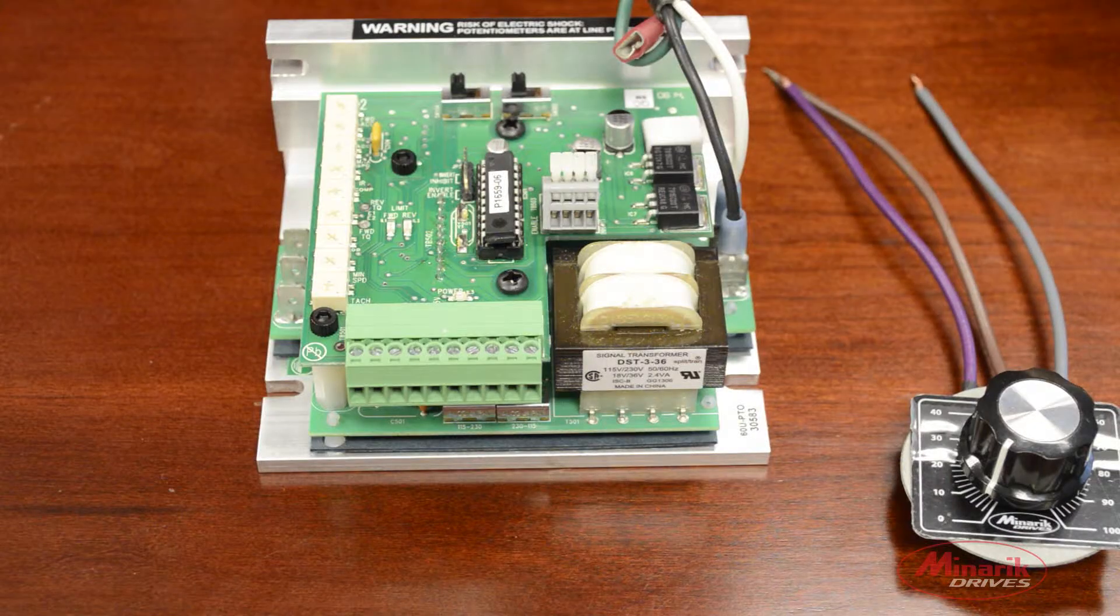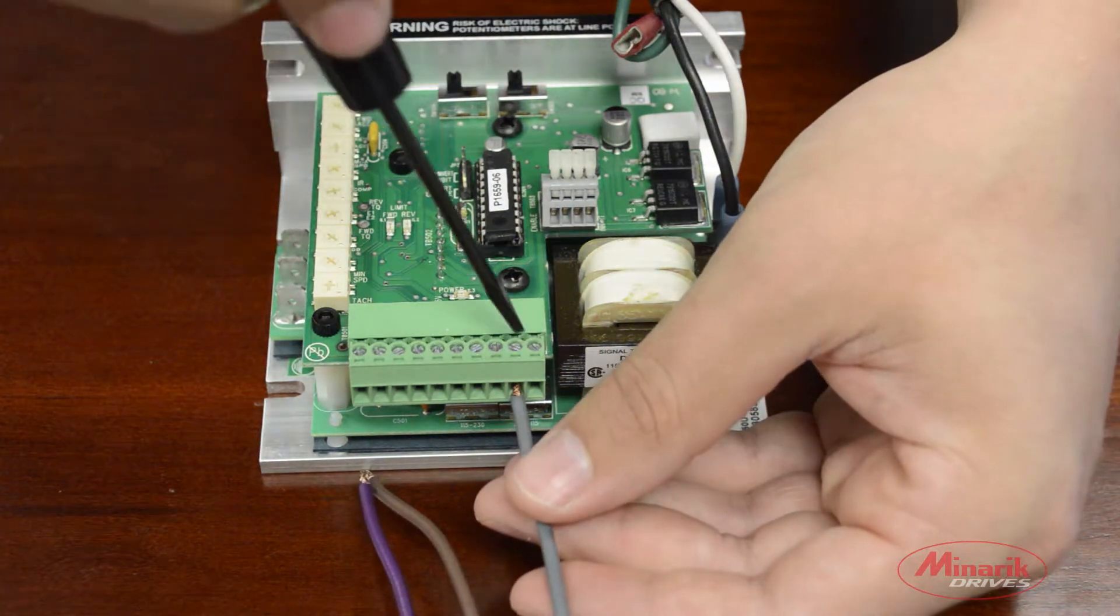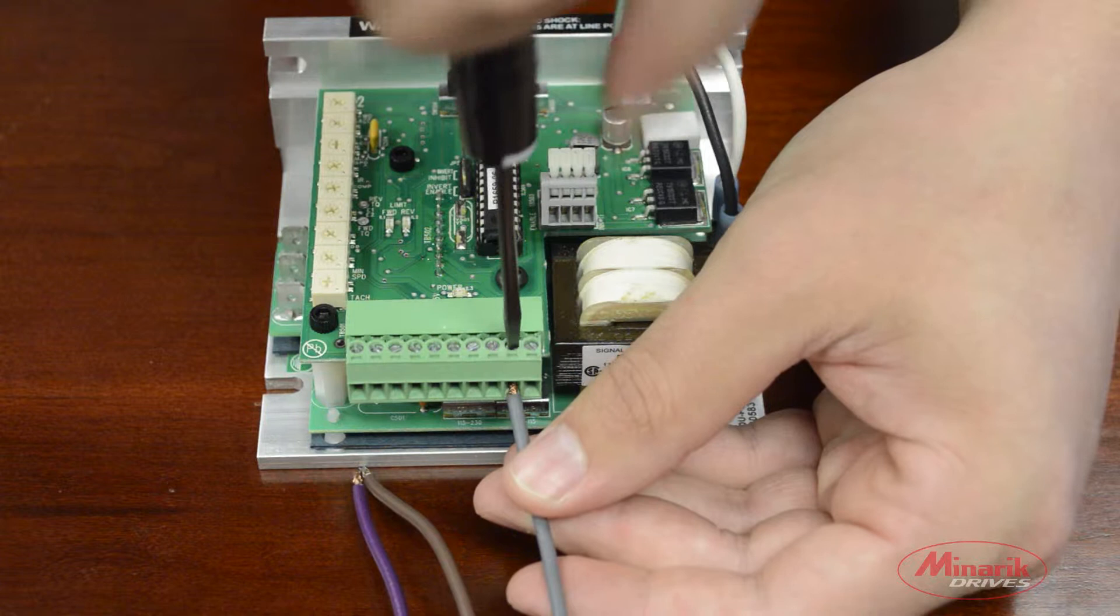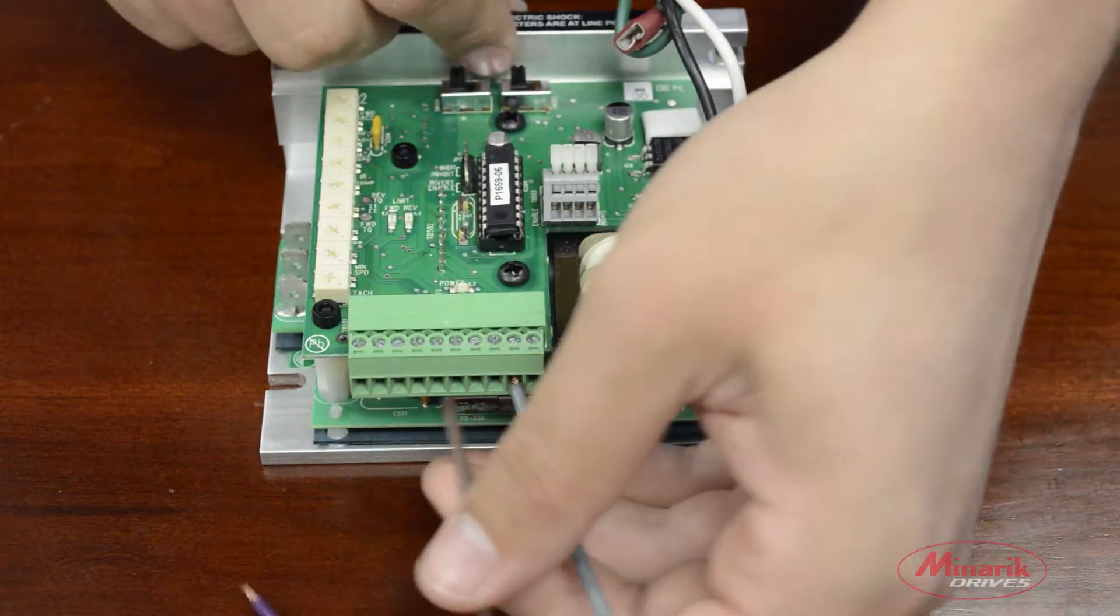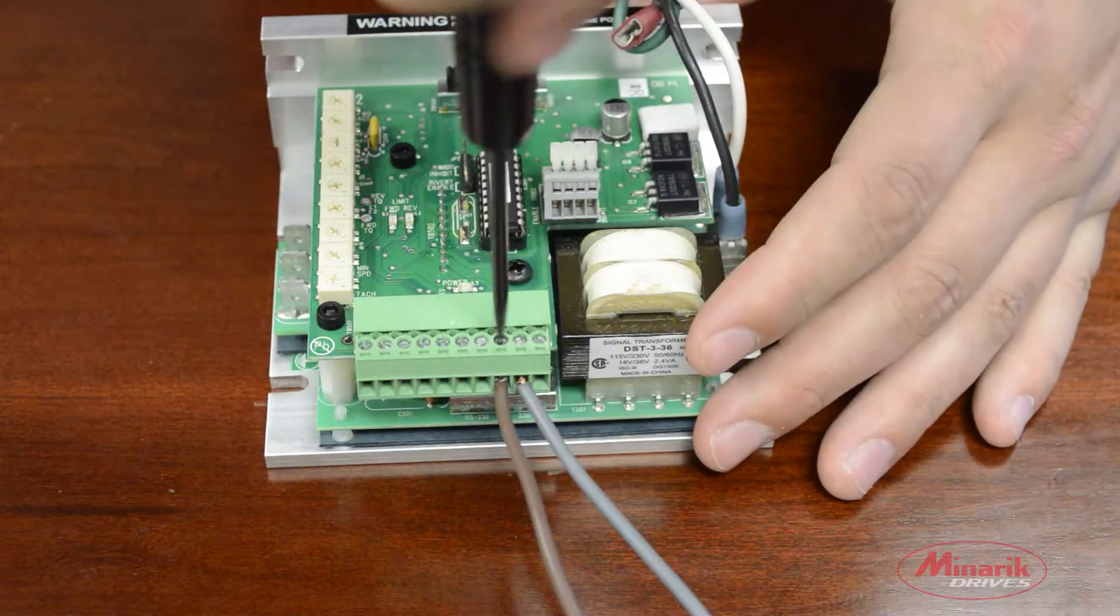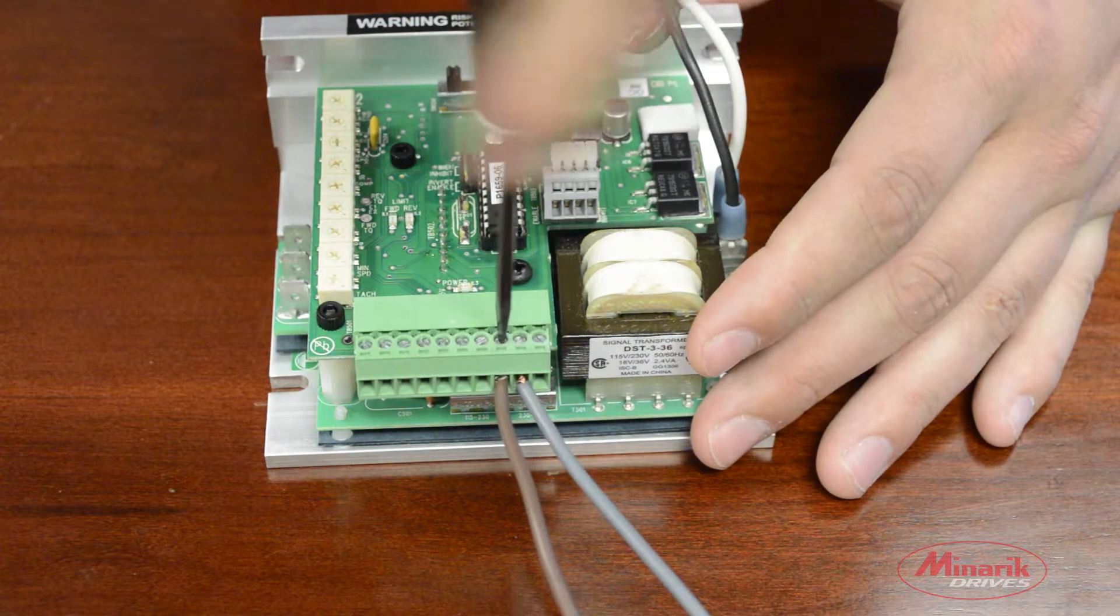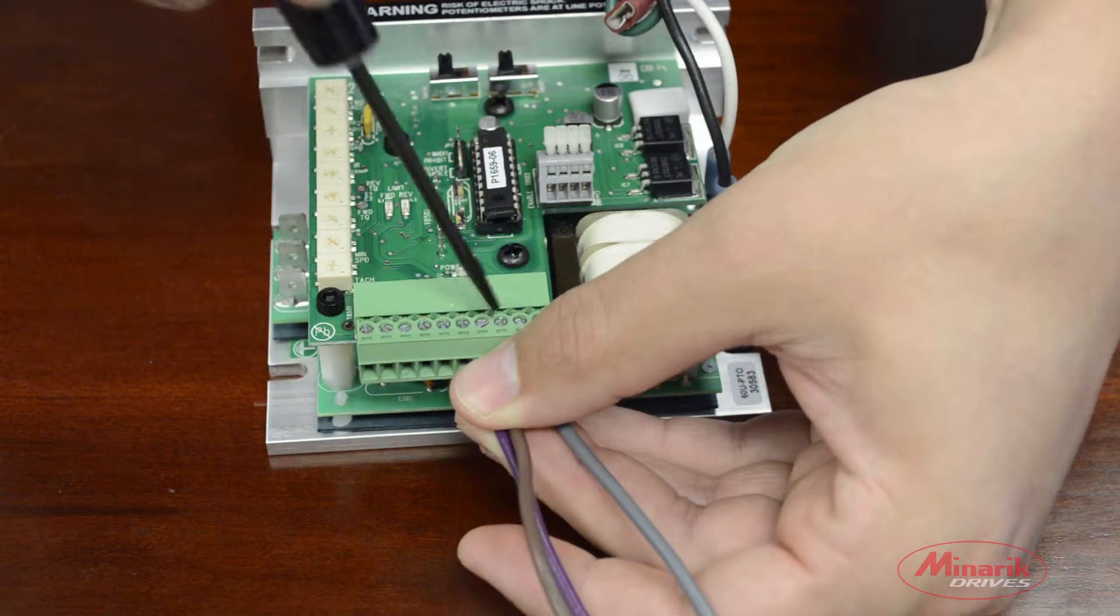Next we'll wire up the drive for bi-directional operation. Take the common wire of the speed pot and put it into S1, the wiper goes into S2, and the positive to S3.